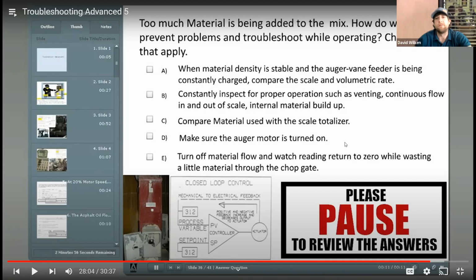So that first option is comparing your flow scale. You have a flow scale being fed by your dust auger. If you're normally running your dust auger at a certain speed, you know what your scale reads at that speed - you can kind of estimate a volume, or if it's calibrated volumetrically, even more directly, though in this scenario it's probably not. But if you have an idea, like Steve was saying, write down things when they're working, it's good to know how they're working. When you're normally running 10 tons per hour of dust into your mix, you probably have a good idea of what speed you're running at when you do that. So if it starts to widen out or become different than that, that's a good check to do as you're running - it can tell you your scale's not lying to you. So do you think that's a good idea, to compare your scale reading with a volumetric rate? Yeah, so you can find out on the fly.